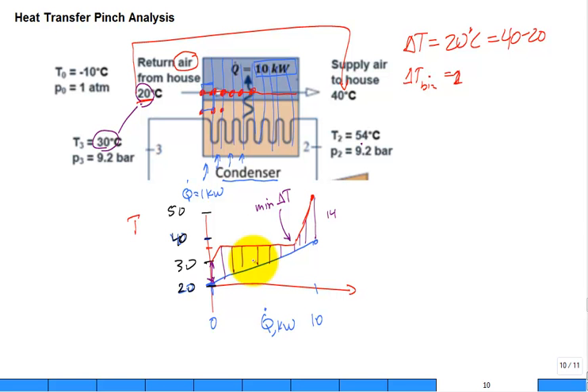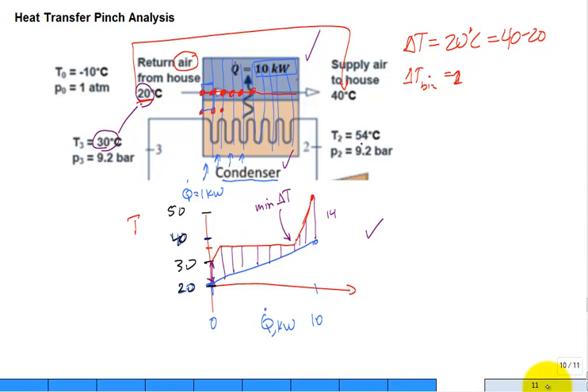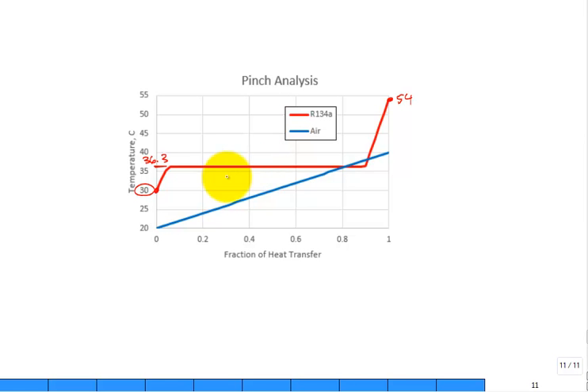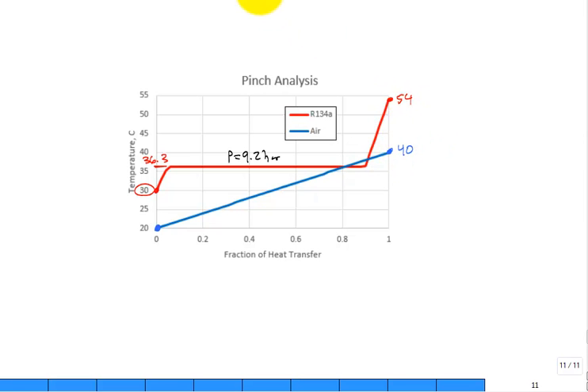What I want to do is first show you the plot for refrigerant 134A in this condenser with the air side, using 100 bins. On the next plot, I've made that calculation. The refrigerant comes in at 54 degrees C, exits at 30 degrees C, with the flat region at 36.3 degrees C — that's the saturation temperature at 9.2 bar. The air comes in at 20 and leaves at 40. And what we find is that the pinch temperature goes down, down, down — and then we have a problem right here.